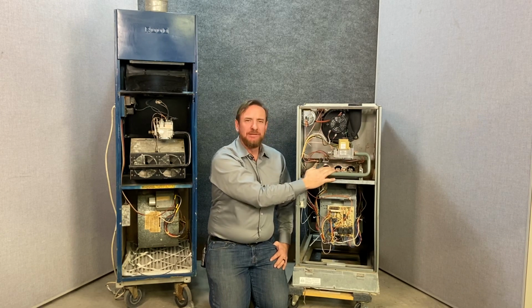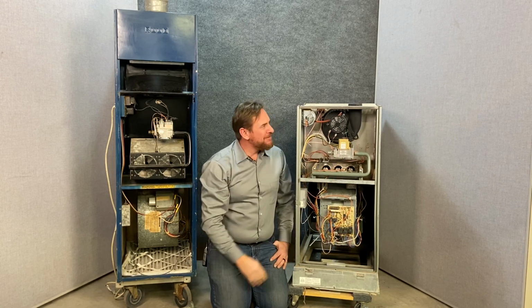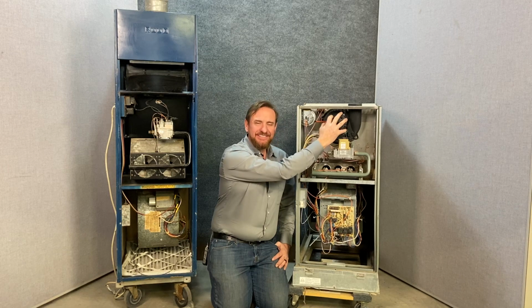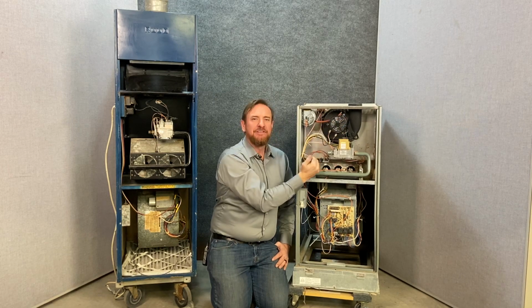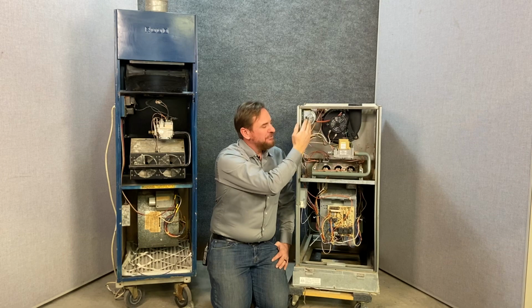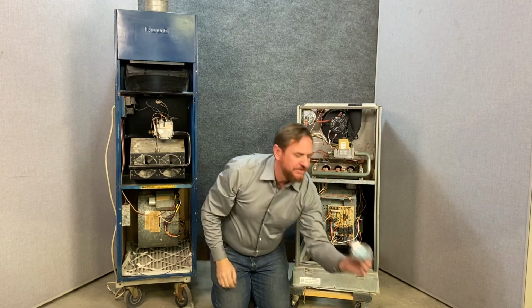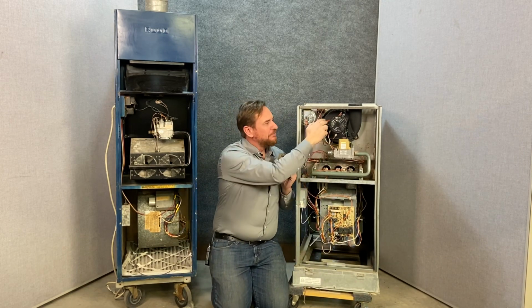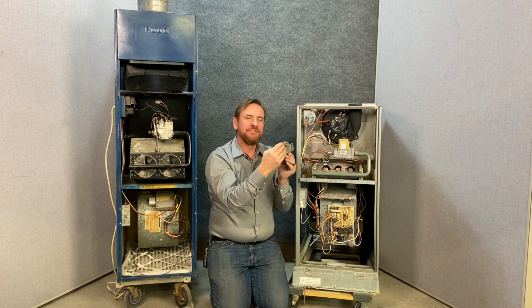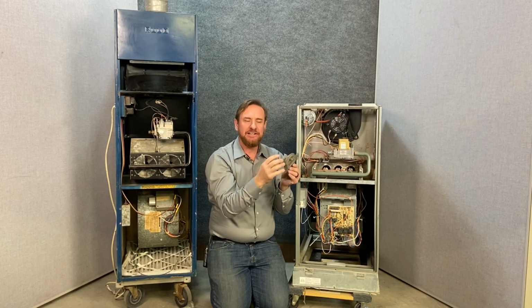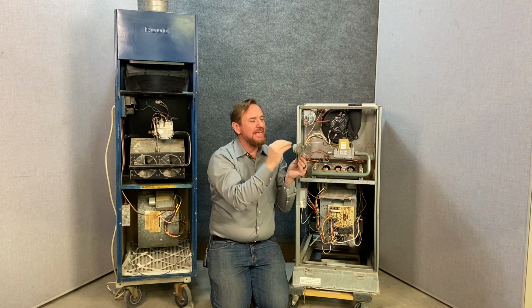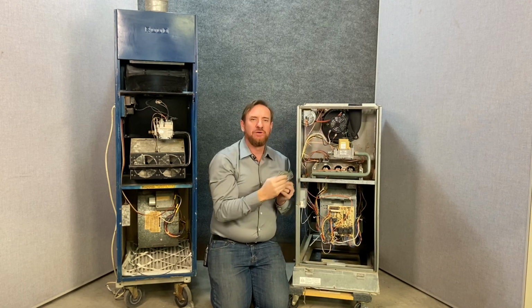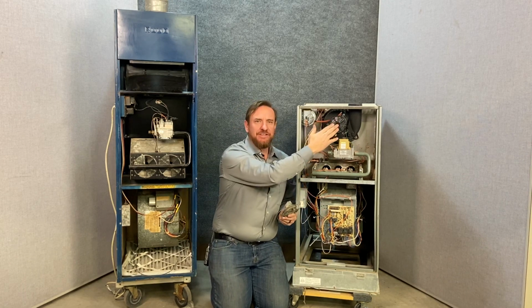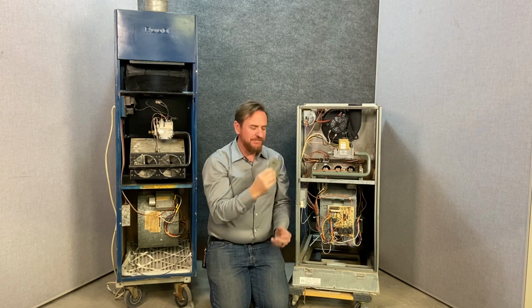So they made it a lot simpler for you to work on. Now, the problem is if this fan motor stops working, it's going to be an issue because there's nothing keeping the flames pulled in. So they've also added this pressure switch. This pressure switch is a pretty simple device. When this is pulling a vacuum through the heat exchanger, it pulls a vacuum to this pressure switch, or negative pressure switch as it's called sometimes. And this tells the control board, hey, this guy's working. So you have this as a safety feature, as well as you have a second safety feature here, as well as the flame rollouts.